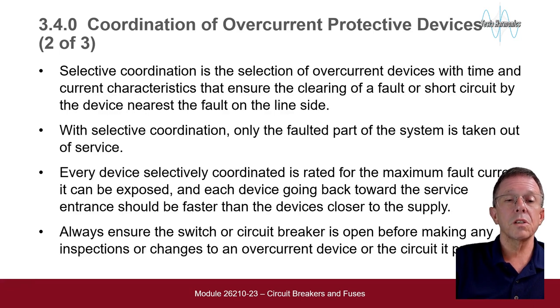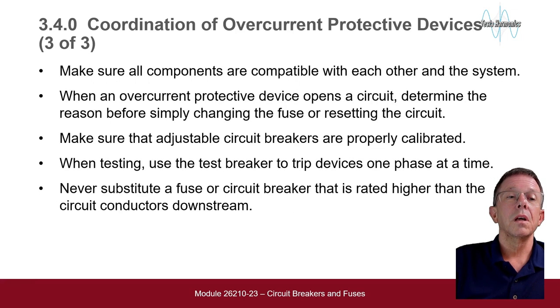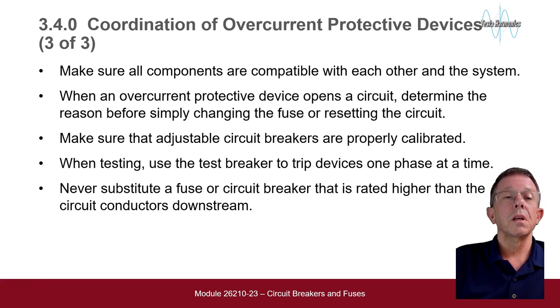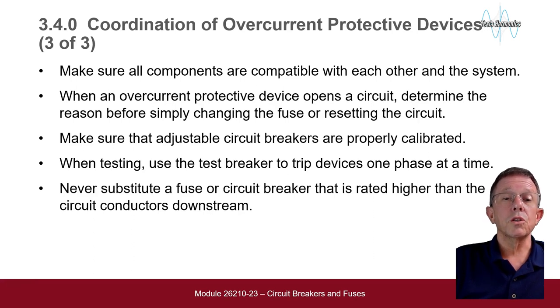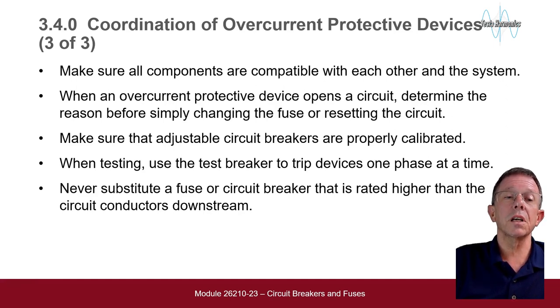Always ensure the switch or circuit breaker is open before making any inspections or changes to an overcurrent device or the circuit it protects. Make sure all components are compatible with each other and the system. When an overcurrent protective device opens the circuit, determine the reason before simply changing the fuse or resetting the circuit. Make sure that adjustable circuit breakers are properly calibrated. When testing, use the test breaker to trip devices one phase at a time. Never substitute a fuse or circuit breaker rated higher than the circuit conductors downstream.